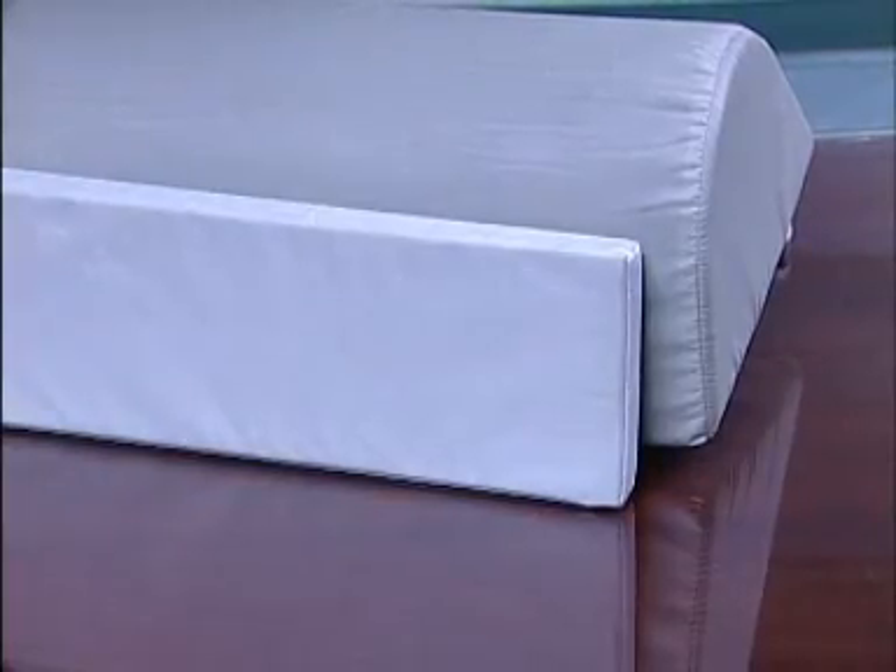All pads should be tested using a black light to detect contamination by body fluids. Biological materials remaining on the pads will light up under black light exposure. This is an excellent way to confirm that your cleaning procedures are adequate and that the covering material is not frayed.